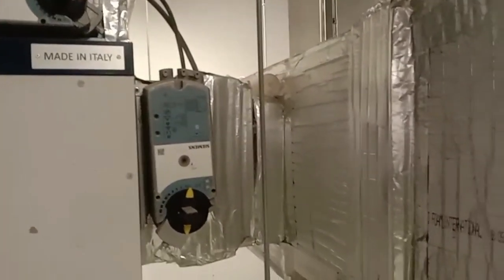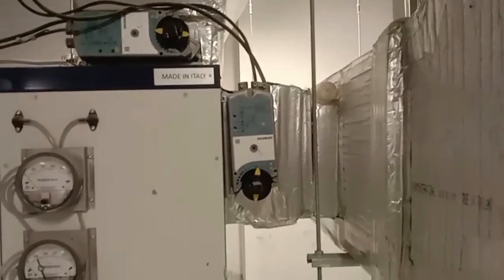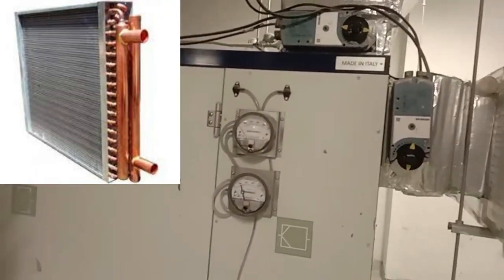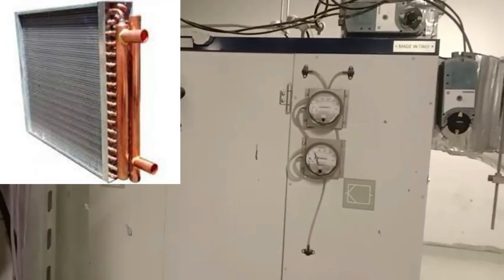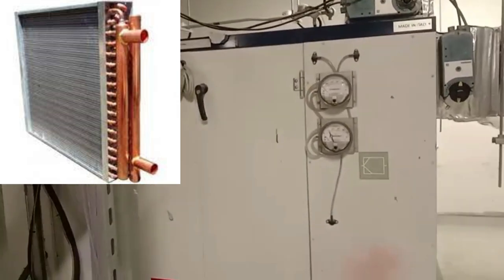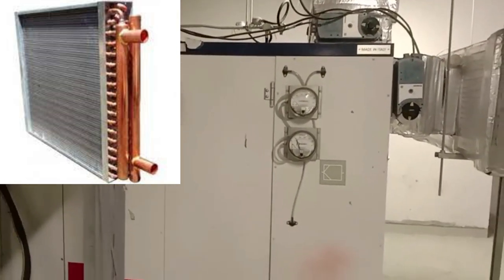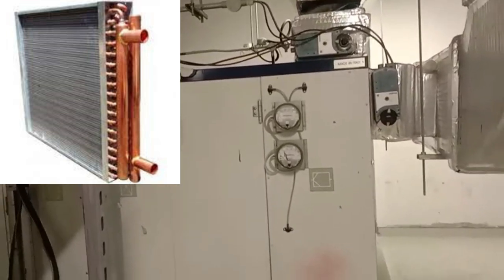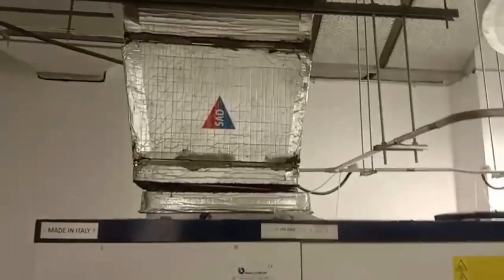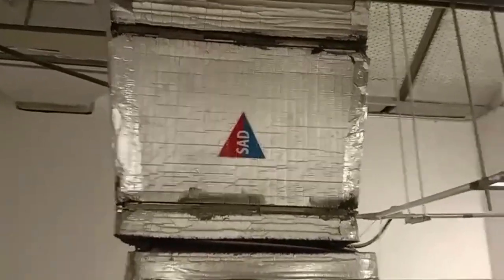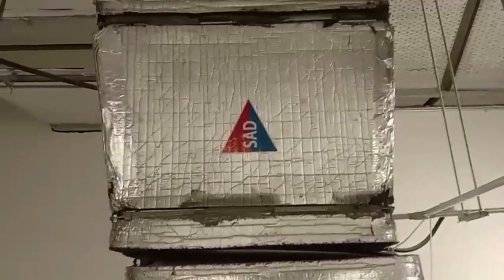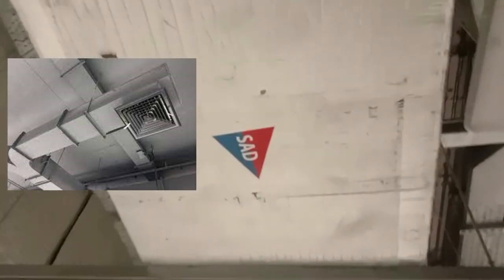So as you can see, once we have the air moving inside the AHU, right inside we have some heat exchangers, which will be able to change whatever temperature you require, and then we'll get the desired temperature at the output. On the other side, we have our supply air duct, which is the conditioned air that is leaving from the AHU going into the building or to the desired location. As you can see, this is the supply air duct.